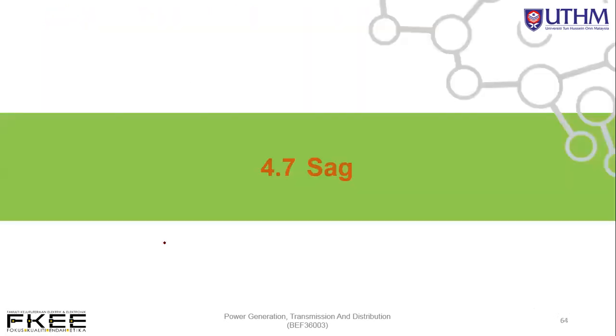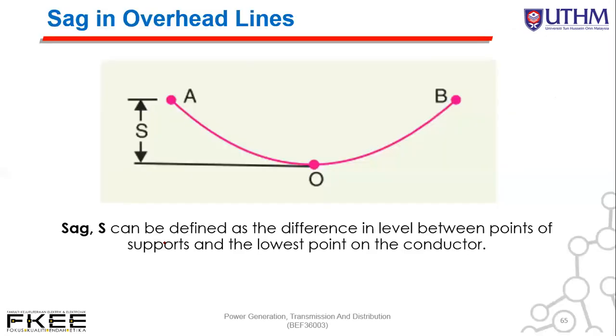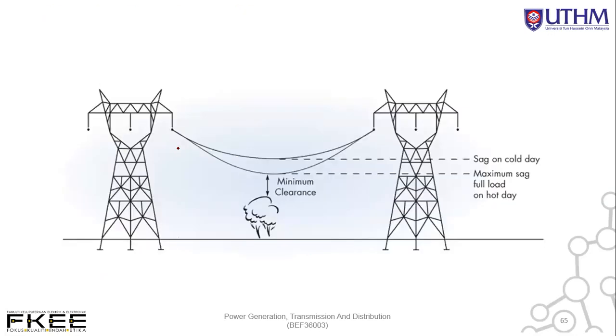Now we look at sag. Sag is the difference in level between the points of support and the lowest point on the conductor — i.e., how much the conductor droops. For example, between tower A and tower B, the conductor in the middle is the lowest point — that distance is the sag. Sag can vary depending on weather: on a cold day it is less, on a hot day the conductor sags more due to thermal expansion. There must always be a minimum clearance between the sag and objects below (trees, ground).